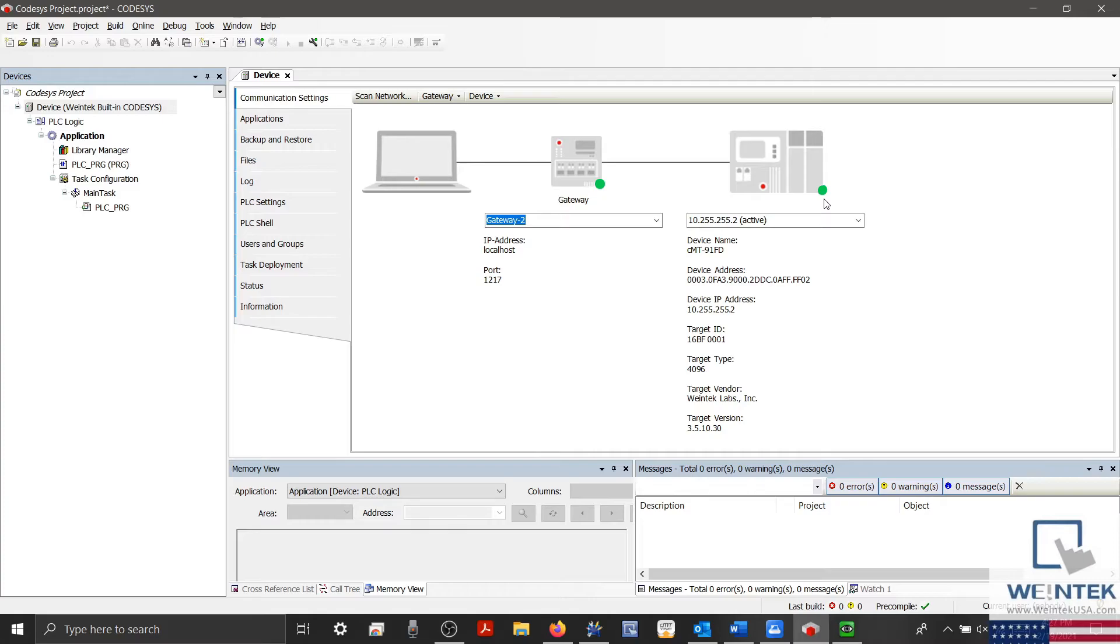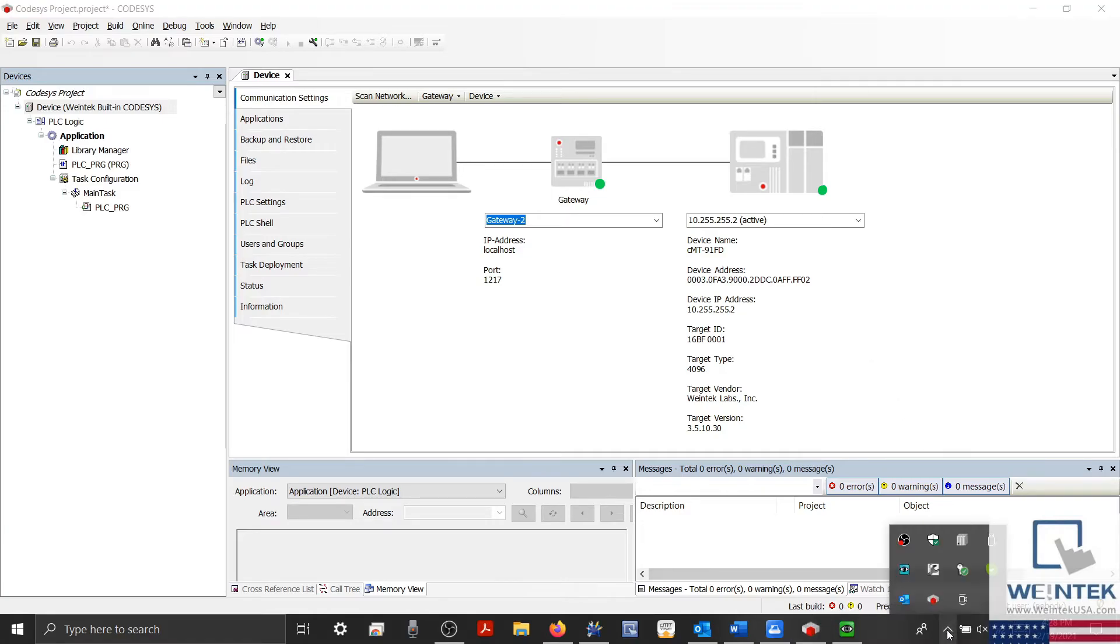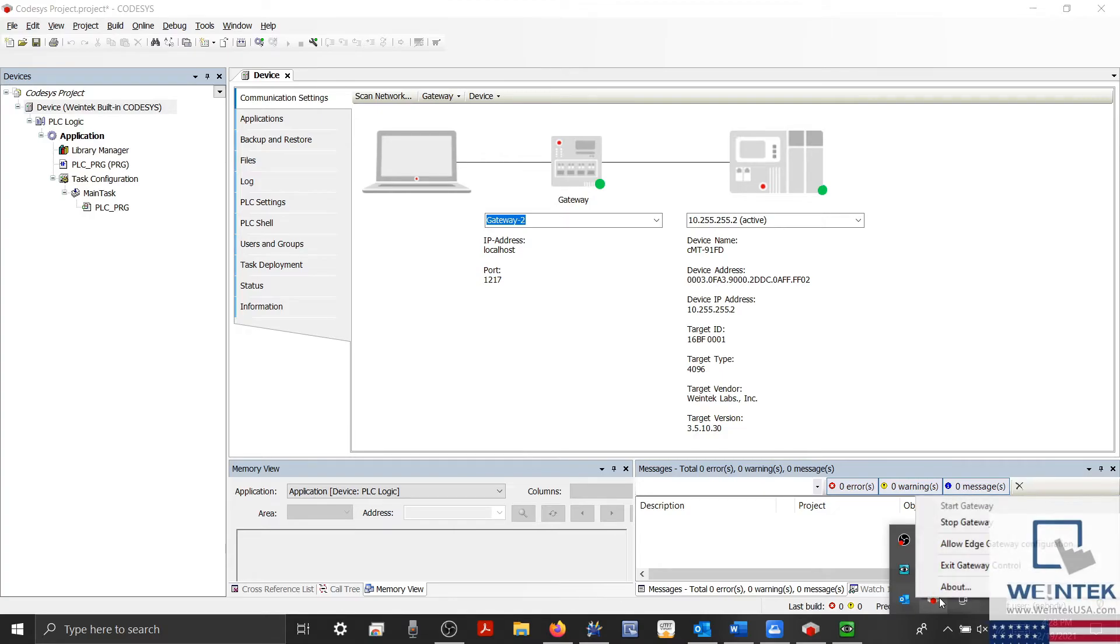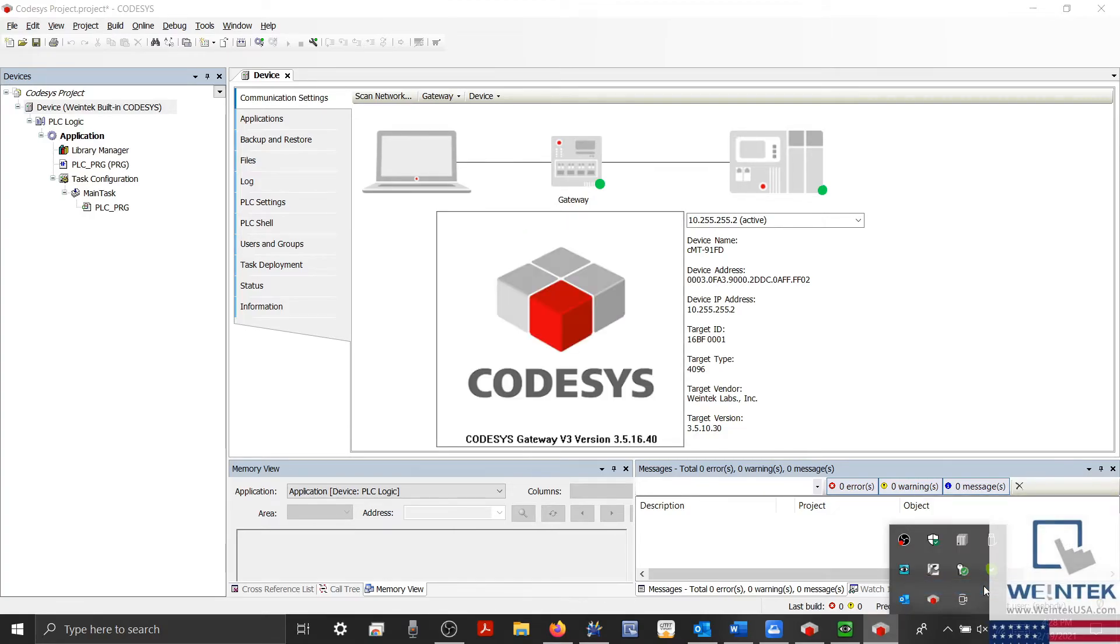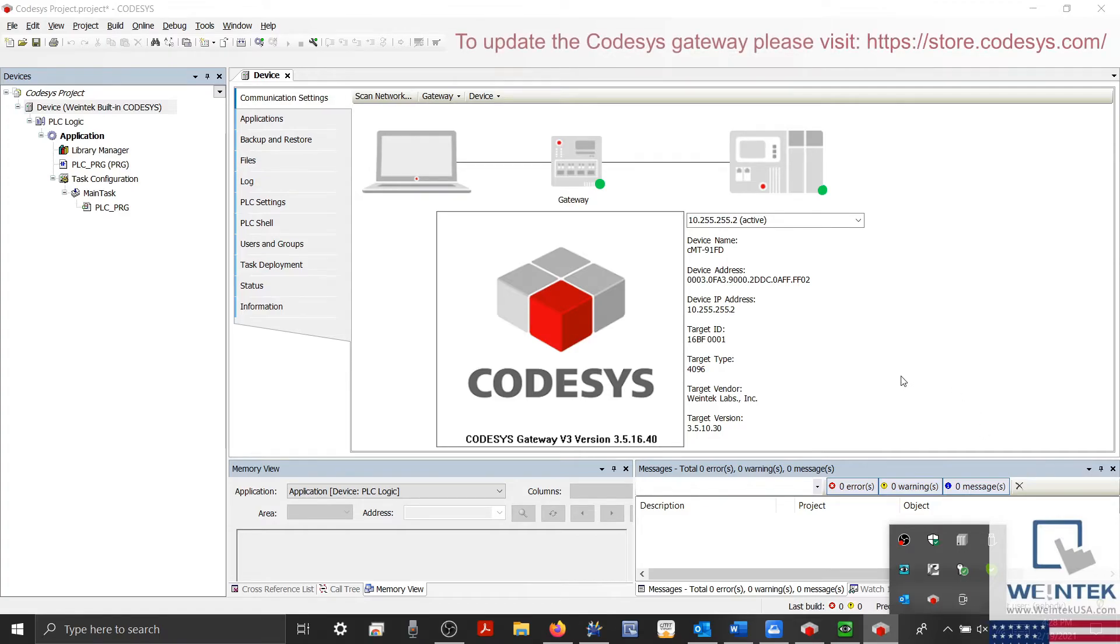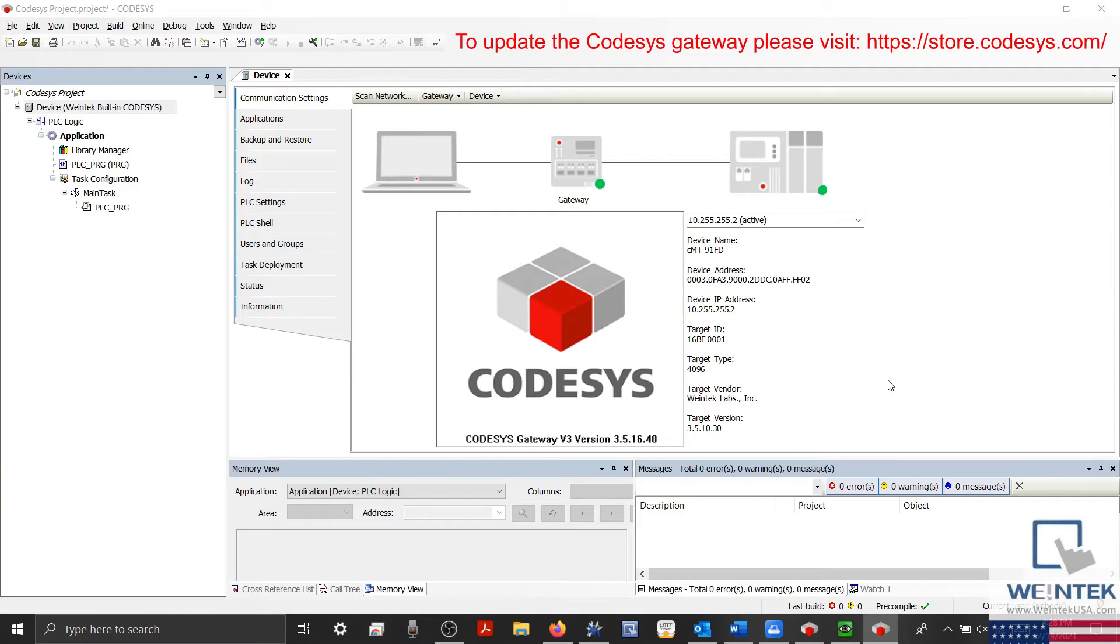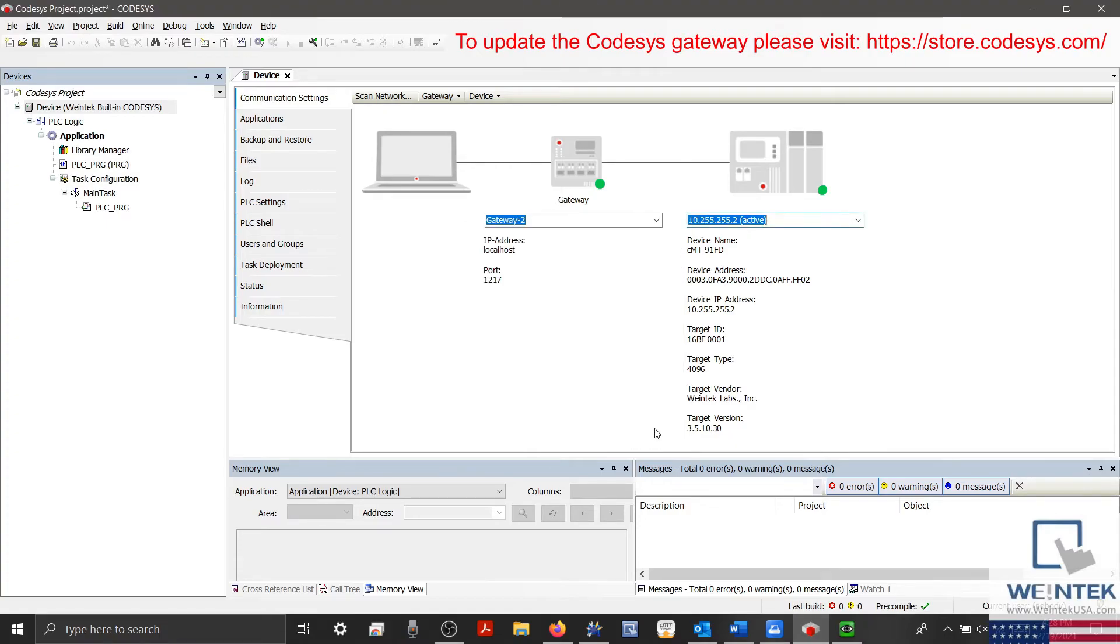And with that, I'd like to mention that the Codesys gateway installed with version 3.5.10.30 may occasionally experience issues when attempting to connect with our Codesys-equipped HMIs through pass-through. When this occurs, our support team recommends that you update your gateway application to a later version. For example, the Codesys gateway installed on my PC is version 3.5.16.40. This update should resolve communication issues and ensure a stable connection.